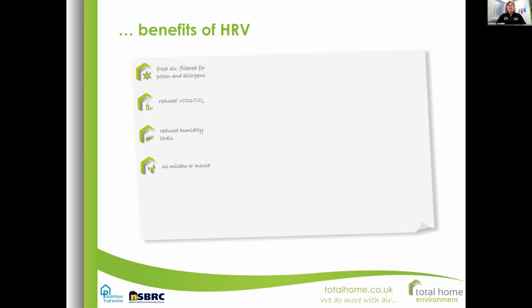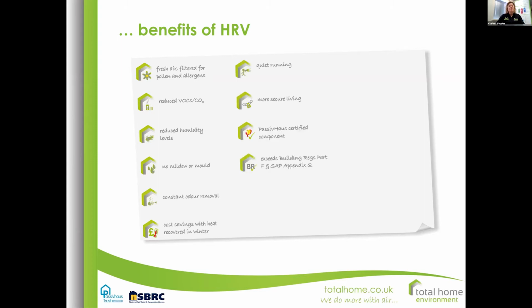So briefly going over the main benefits of heat recovery, it's lovely fresh filtered air, getting rid of all those nasty chemicals and humidity, so dust mites won't be so prevalent. So, you know, another plus point for allergy sufferers. Again, you won't have to worry about redecorating over mold and mildew stains and wiping that mirror down after a shower. All that moisture is going to be removed. Obviously, with the whole house air change, you're going to be getting rid of odors all the time and recycling 95% of the heat that you would normally lose. Obviously, you're going to get cost savings, especially over winter.